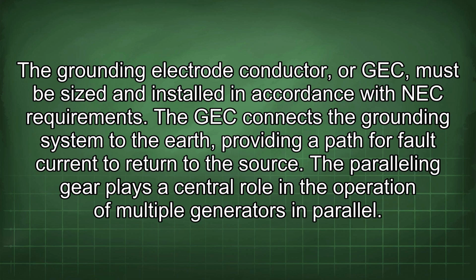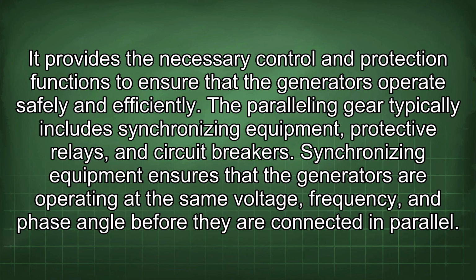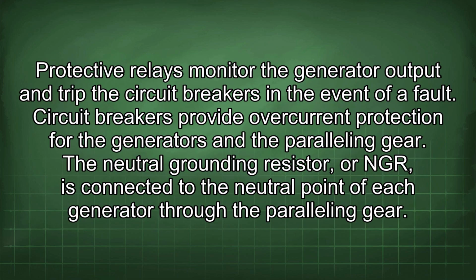The paralleling gear plays a central role in the operation of multiple generators in parallel. It provides the necessary control and protection functions to ensure that the generators operate safely and efficiently. The paralleling gear typically includes synchronizing equipment, protective relays, and circuit breakers. Synchronizing equipment ensures that the generators are operating at the same voltage, frequency, and phase angle before they are connected in parallel. Protective relays monitor the generator output and trip the circuit breakers in the event of a fault. Circuit breakers provide overcurrent protection for the generators and the paralleling gear.